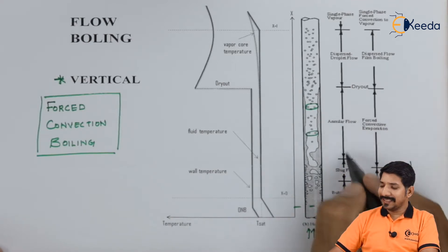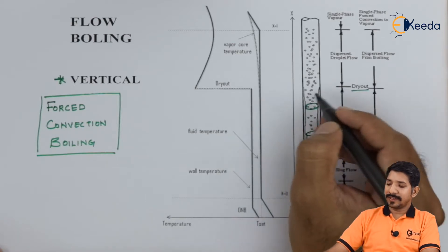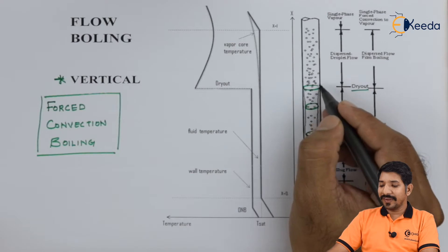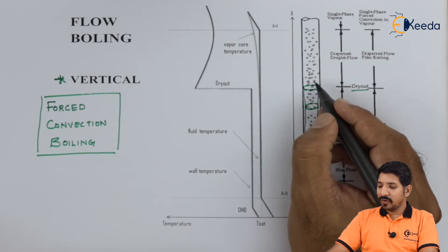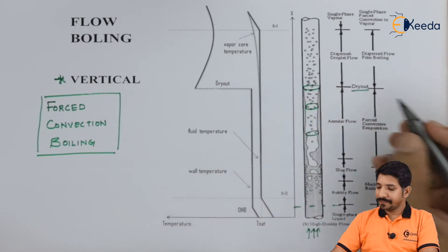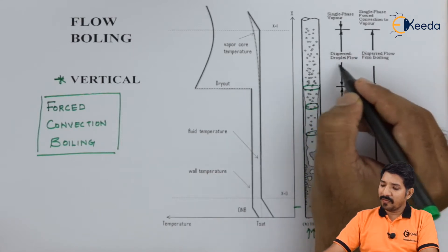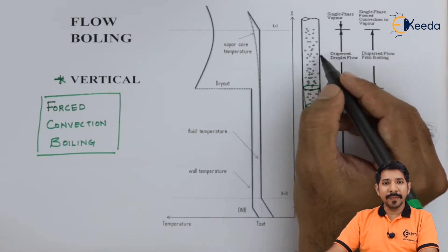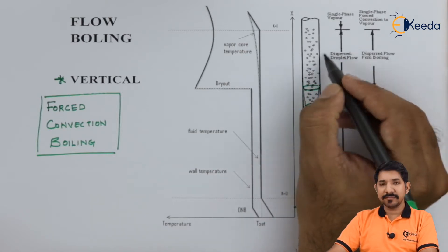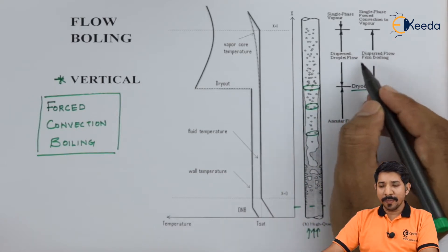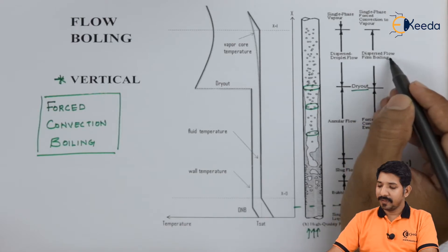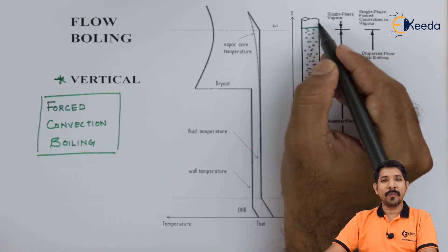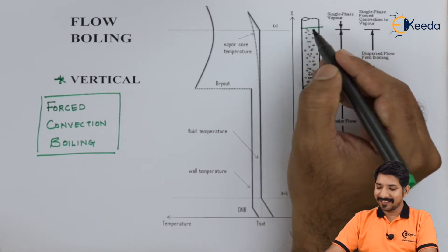Now comes the dry out. The dry out is the point where the maximum annular ring is formed — meaning no surface of the pipe is covered by fluid anymore; the entire region has only steam. Beyond dry out, a dispersed droplet flow occurs — this is called mist flow. In mist flow there is vapor with small droplets suspended in it. The heat transfer is predominantly by dispersed flow film boiling.